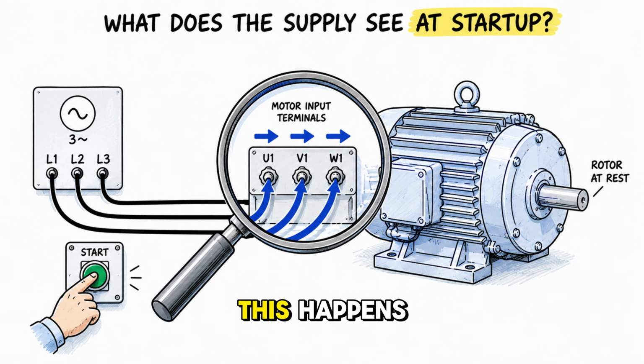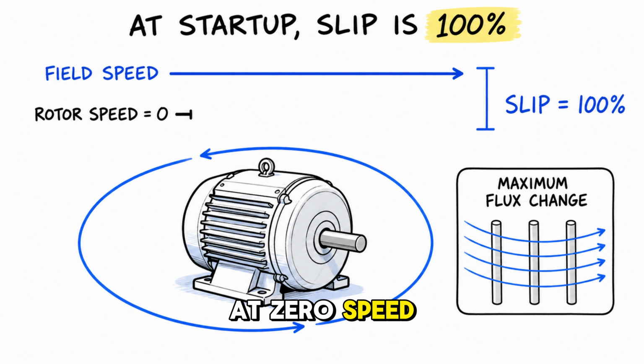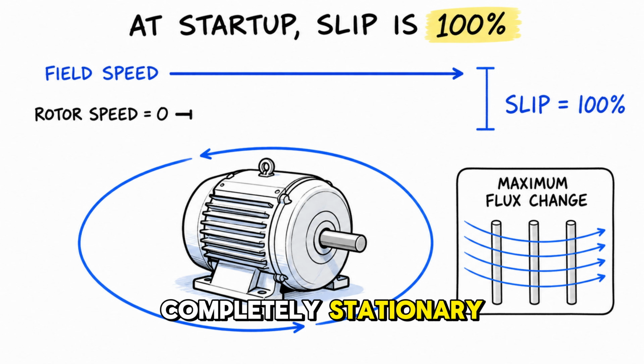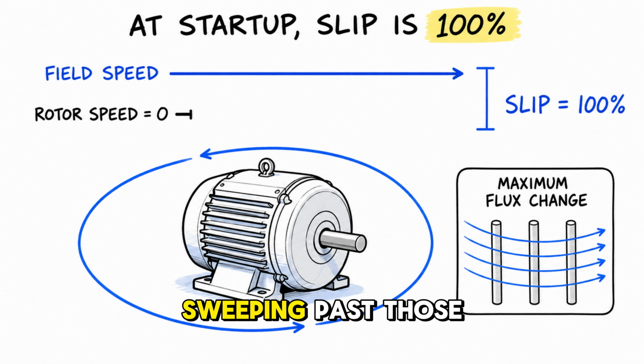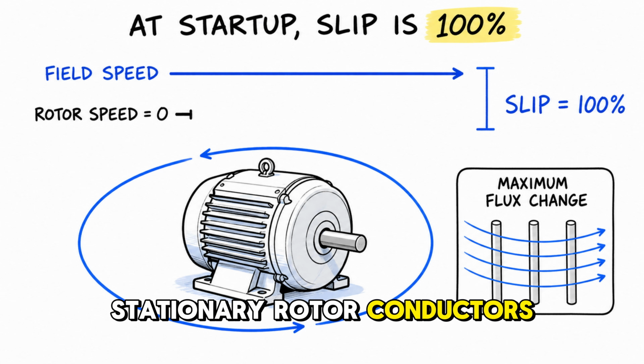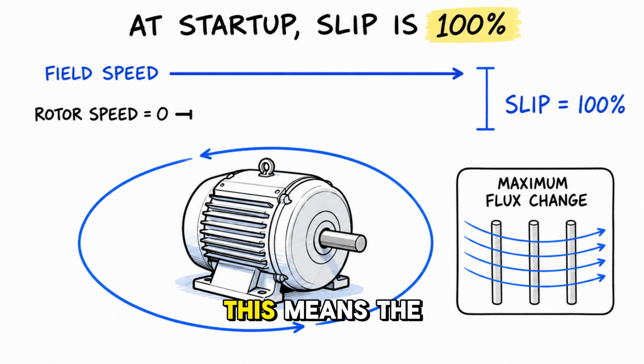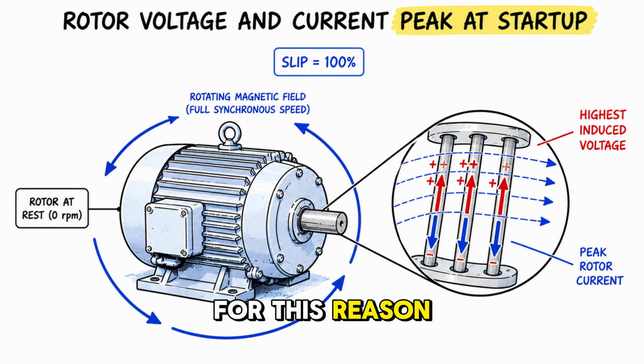To understand why this happens, you need to look at what the motor looks like to the power supply at the exact moment of starting. At 0 speed, the rotor is completely stationary. The rotating magnetic field is sweeping past those stationary rotor conductors at full synchronous speed. This means the slip is at 100%. The rate of flux change is at its absolute maximum. For this reason, the voltage induced in the rotor is at its highest point.